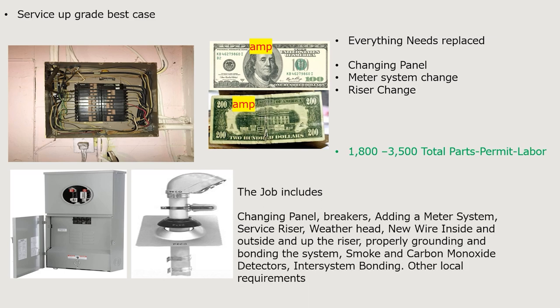This service upgrade job includes changing the panel and breakers, the meter system, weather head, new inside and outside wire, replacing the riser pipe and riser wire, properly grounding and bonding the system, smoke and carbon monoxide detectors, inter-system bonding, and other local code requirements. I hope this has given you a good idea of what it takes, what it entails when changing a panel, and what the cost is going to be.